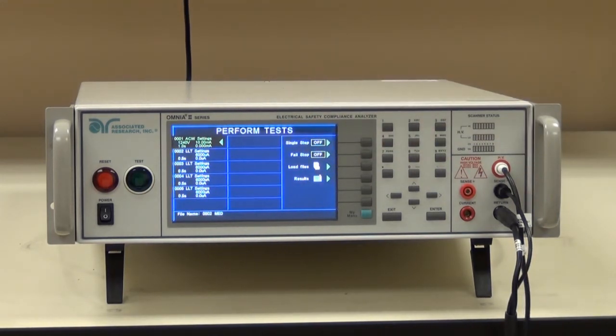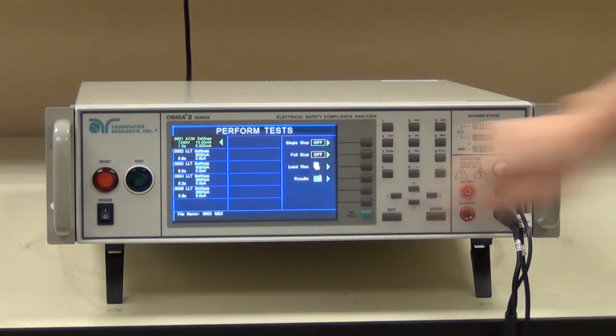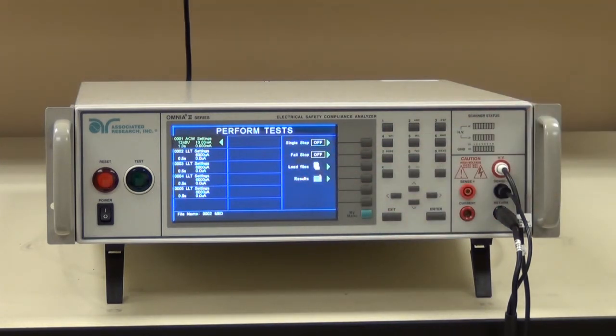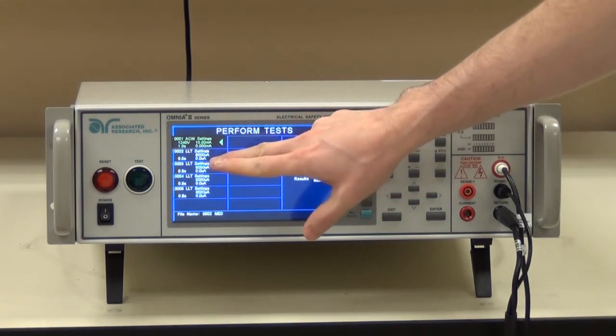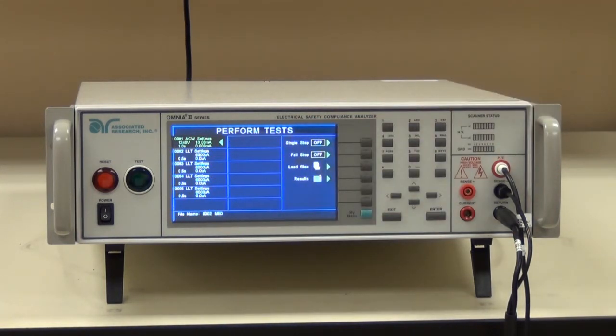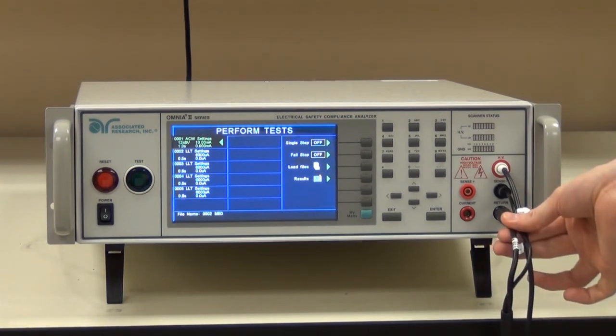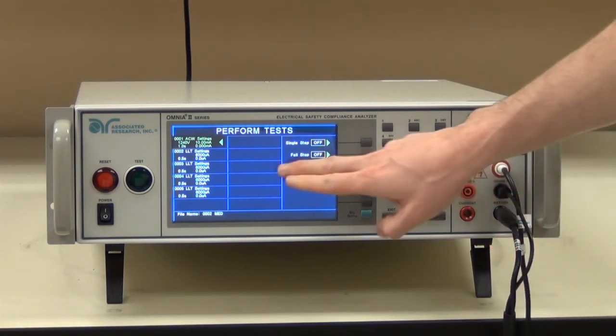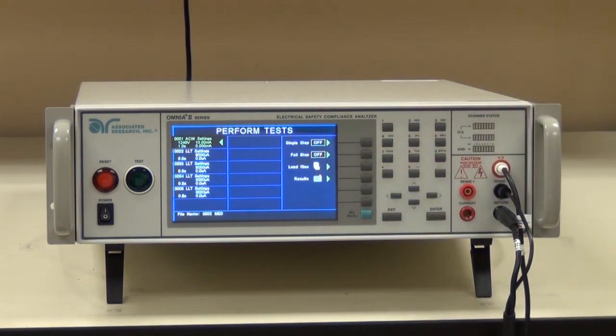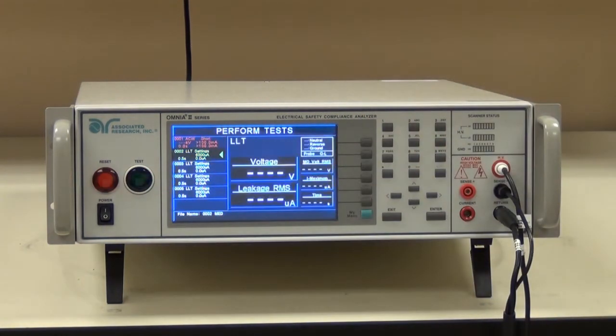The second consideration is to utilize the fail stop feature. As we discussed in a prior video, with fail stop on, the test sequence will stop upon a failure. So if your high pot test fails, this means it's not going to continue on to the line leakage tests. What I've done here is I've actually shorted my high voltage and return to purposely cause a fail, and I've turned fail stop off to look at more of a worst case scenario. As you can see here, it continued directly onto the line leakage tests. And this is not the most optimal case, because if the high pot test fails, you may not want to run the other tests.